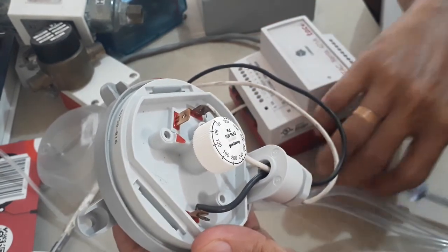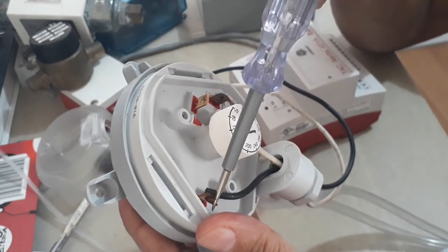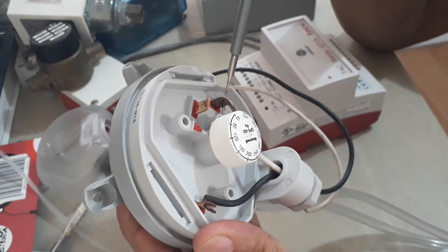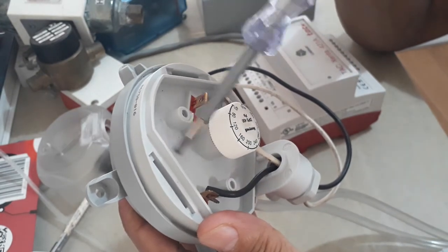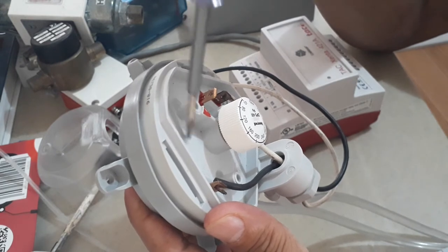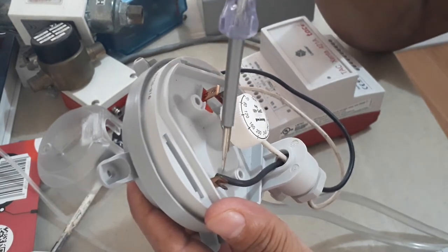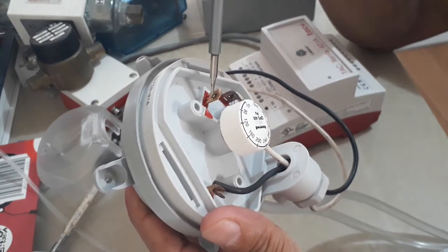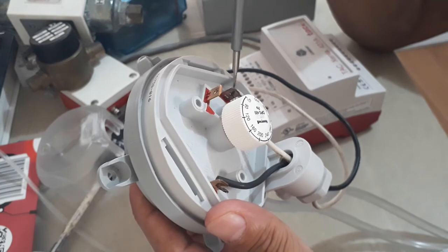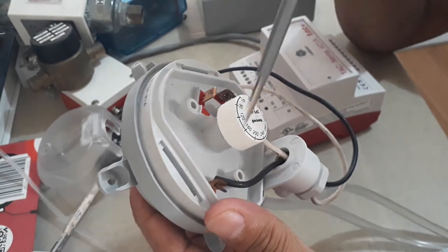Inside you can find three terminals: Common, number 1, and number 2. Based on the terminal connection drawing, Common and 1 is the normally closed contact, and Common and 2 is the normally open contact. When using this for airflow probing, use the normally open contact — so terminals Common and 2.